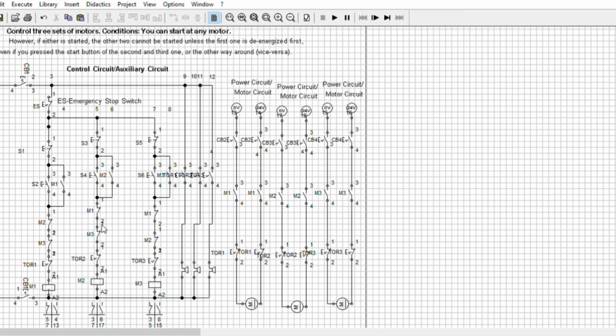The other one is the sequential operation. You can use sequential operation by using the opposite one, normally open contact. We're going to operate this one first, and this one is the next one. We are going to have normally open here, so that this can operate, and all together the three can operate. So that is the sequential. Turn this one on, normally open. Then you can turn this on if the operation stays that way. For sequential, you are going to use normally open. For electrical interlock, you are going to use normally closed. You can also use timers for automatic sequential.